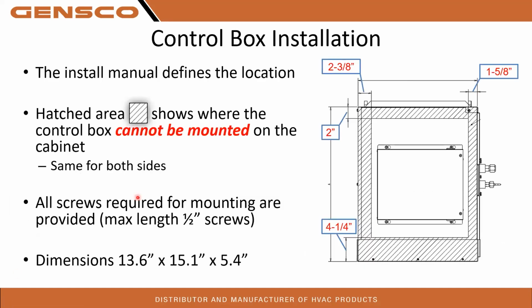If you're mounting it to the coil, there are some no-go zones here. I've marked them out here with the little stripes. Anywhere in the center of the coil, this is marked on the coils for you and in the installation manuals. If you try to screw into these areas, you risk damage to the coil or drain pans. So make sure you stick to the marked area on the inside of the coils to be safe. Do not use screws longer than 1/2 inch. If you try to run 2-inch screws into that thing, you will cause coil damage, and I promise you Mitsubishi is not going to replace that for you.